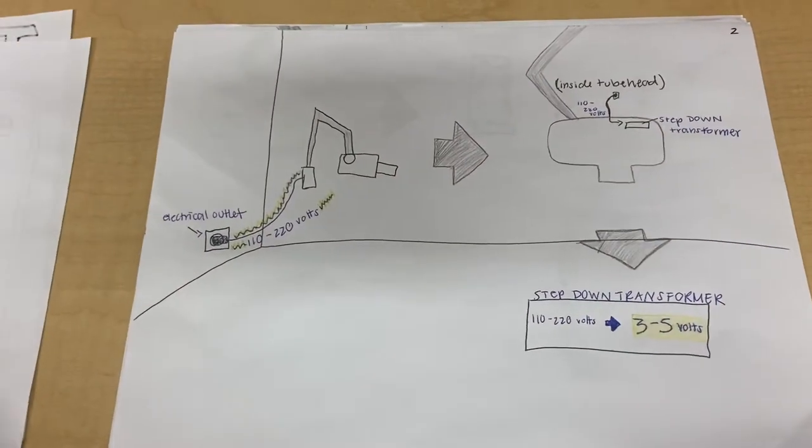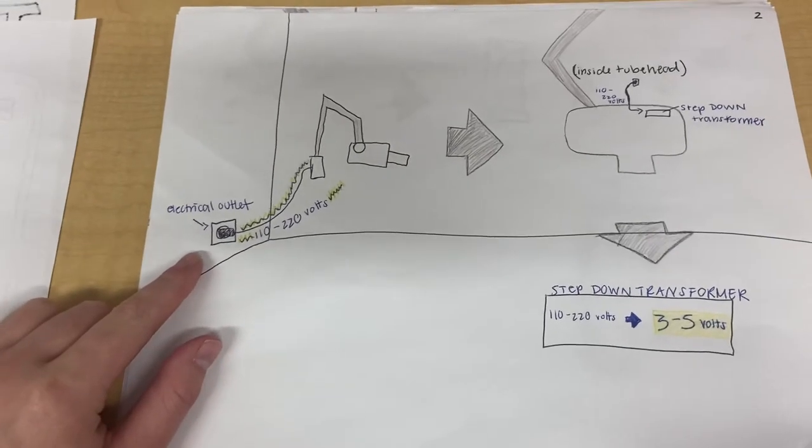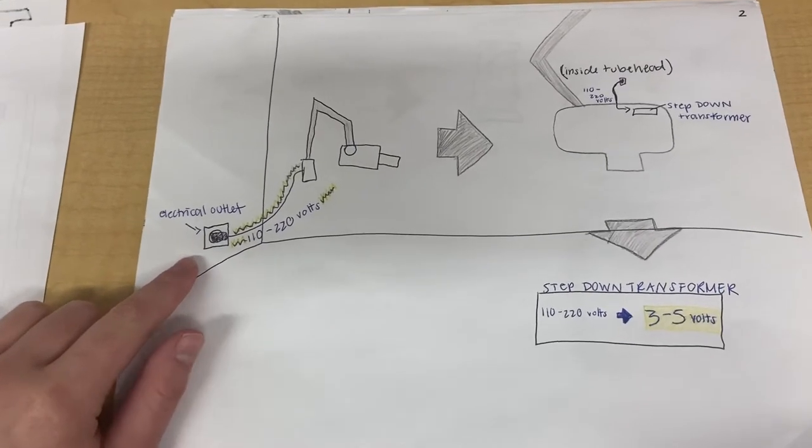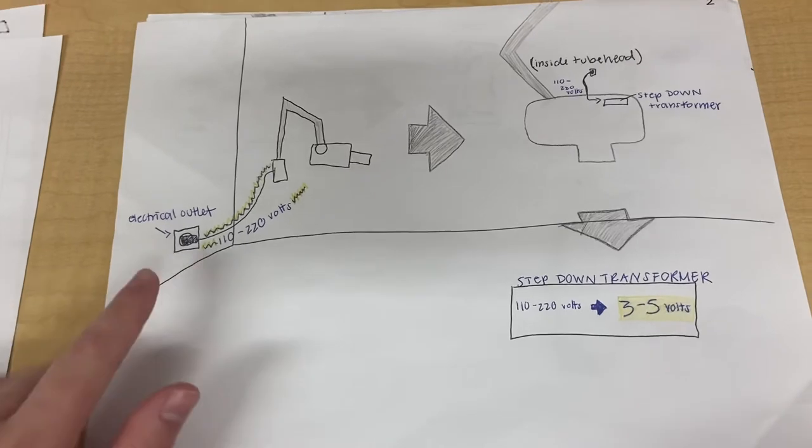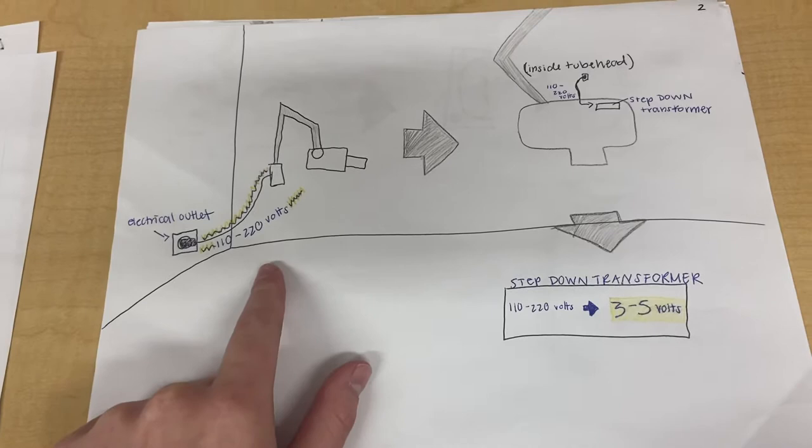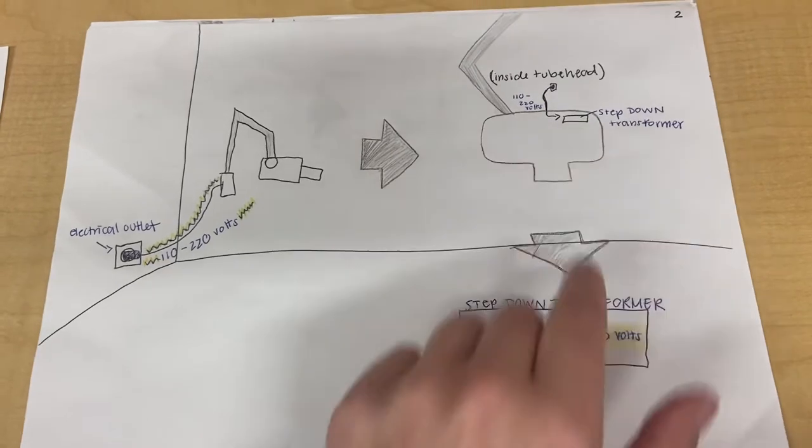Alright, so first off, the X-ray machine will be plugged into the wall, and when it is turned on, the electricity will travel from the outlet to the X-ray machine as 110 to 220 volts. Because the machine doesn't need that many volts yet, it will actually enter the step-down transformer.